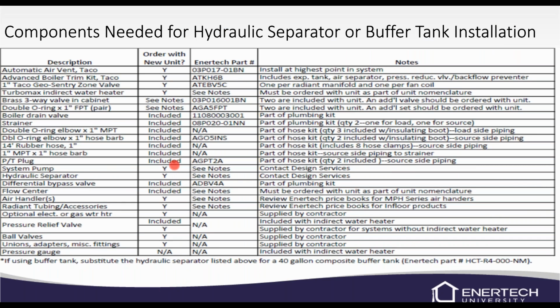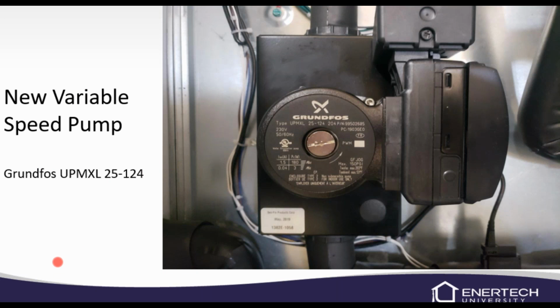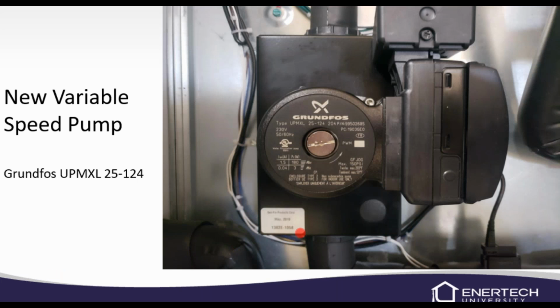Again, some of the components, we kind of already went through this. This is the variable speed pump that we're going to be using going forward. It may not be the one that's in your unit when you get it, but this is the one that's going forward. And it's a UPM XL. It's a 25-124 pump. It is more efficient than the Grundfos UPM or the UP 32-140. It'll do a little bit less pumping, but you probably won't even notice it. It seems to be a good replacement for us. Again, it does use less power.